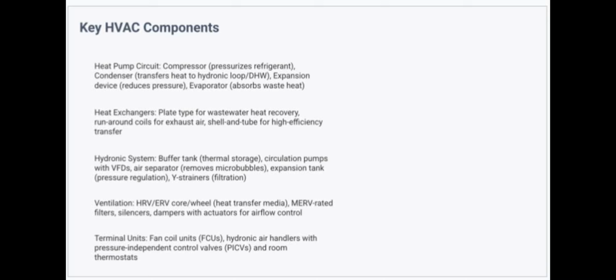The key components I will be using are the heat pump circuit: compressor, condenser, expansion device, evaporator, and heat exchangers: plate type for wastewater heat recovery, runaround coils for exhaust air, and/or shell and tube for high efficiency transfer. Hydronic system: the buffer tank, which holds the thermal storage, circulation pumps with VFDs, air separator, so we can remove the microbubbles, expansion tank, so we can regulate the pressure, and Y-strainers for filtration.